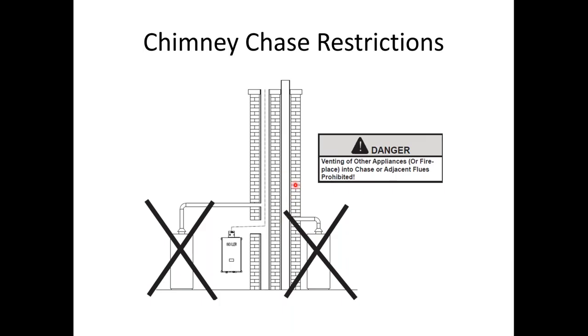If there is a rupture in the flue liners, if that rupture melts stainless steel, they've got bigger problems than just stainless steel melting. It's basically why, if you're doing a polypropylene liner, you can't have the adjacent chimney still being used. Even with the stainless steel liner, the boiler can be the only appliance going into that chimney. No other appliance can vent into there. So if they have a water heater, we either have to sell them a combi, do an indirect tank, or do a power vented water heater.